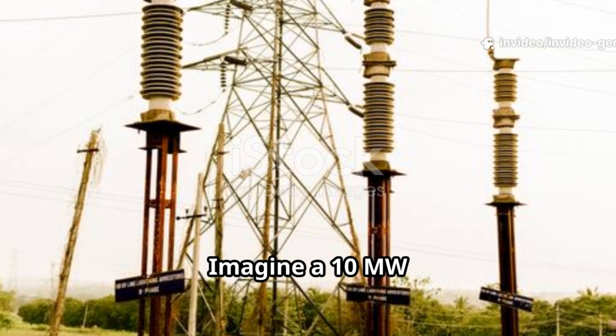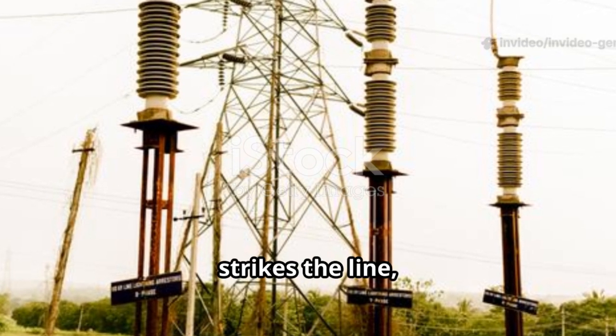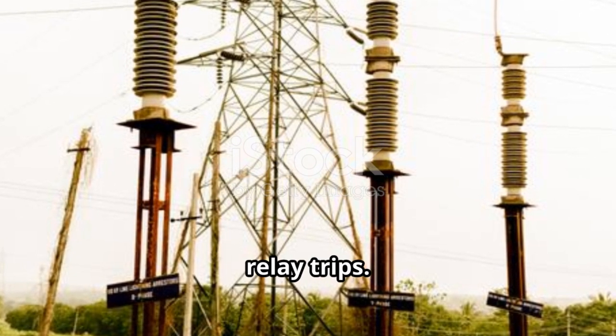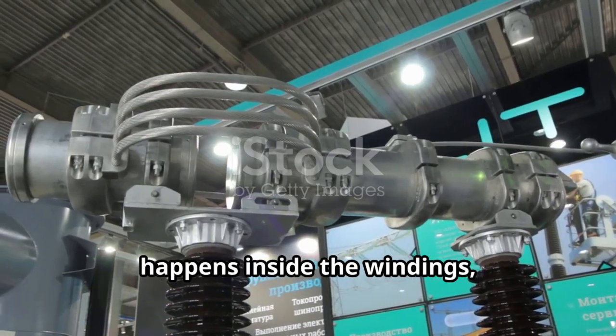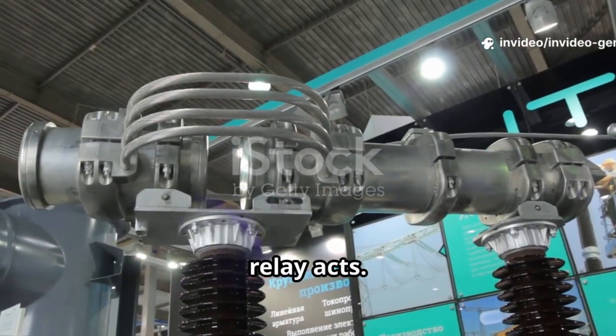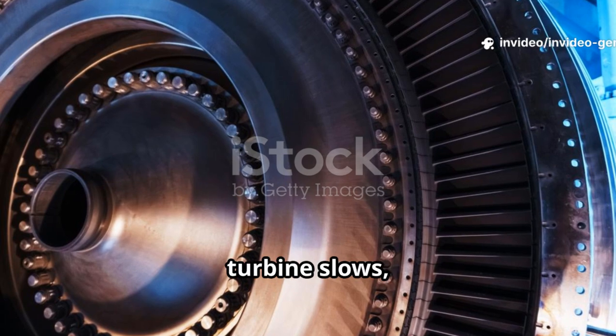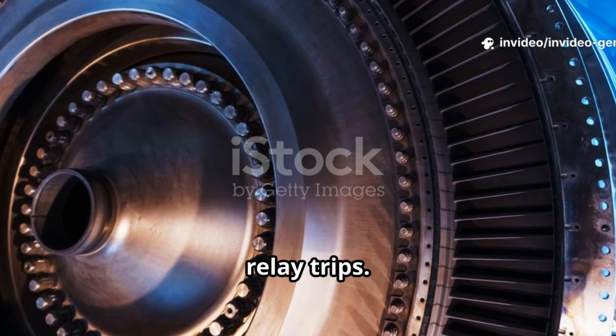Imagine a 10 MW generator running. If lightning strikes the line, the overvoltage relay trips. If a short circuit happens inside the windings, the differential relay acts. If steam supply drops and the turbine slows, the underfrequency relay trips.